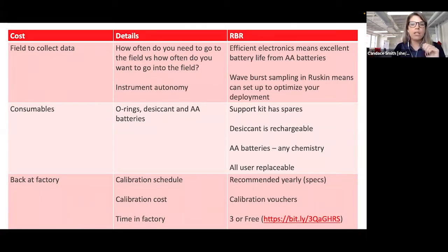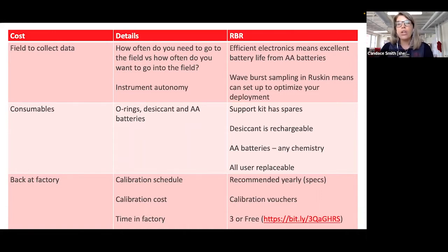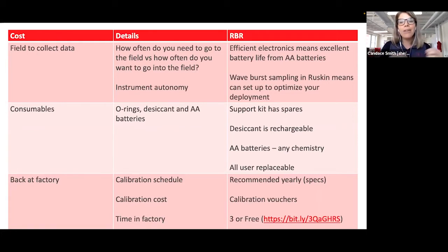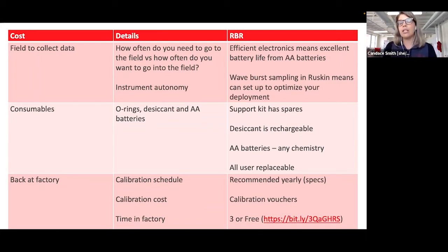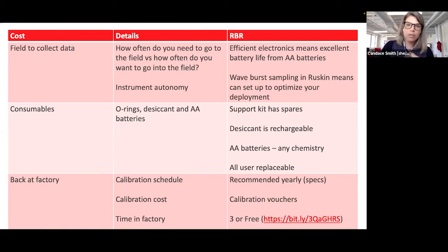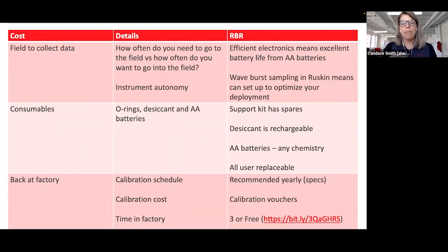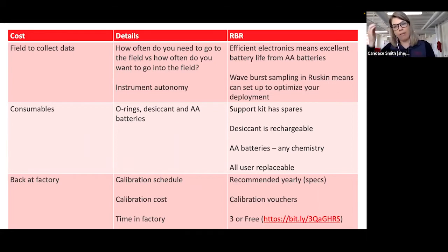The cost of being back at the factory: how often do we recommend calibration? For most of our sensors it is yearly. We have excellent specifications so that the pressure sensor, for example, can detect small surface waves. We sell calibration vouchers when you buy the instrument to encourage yearly calibration — they're a little cheaper than buying calibration when you actually need it. Right now we have a promotion: we'll calibrate your instruments in three weeks or the calibration is free. So back-at-factory time is once a year, hopefully within three weeks.